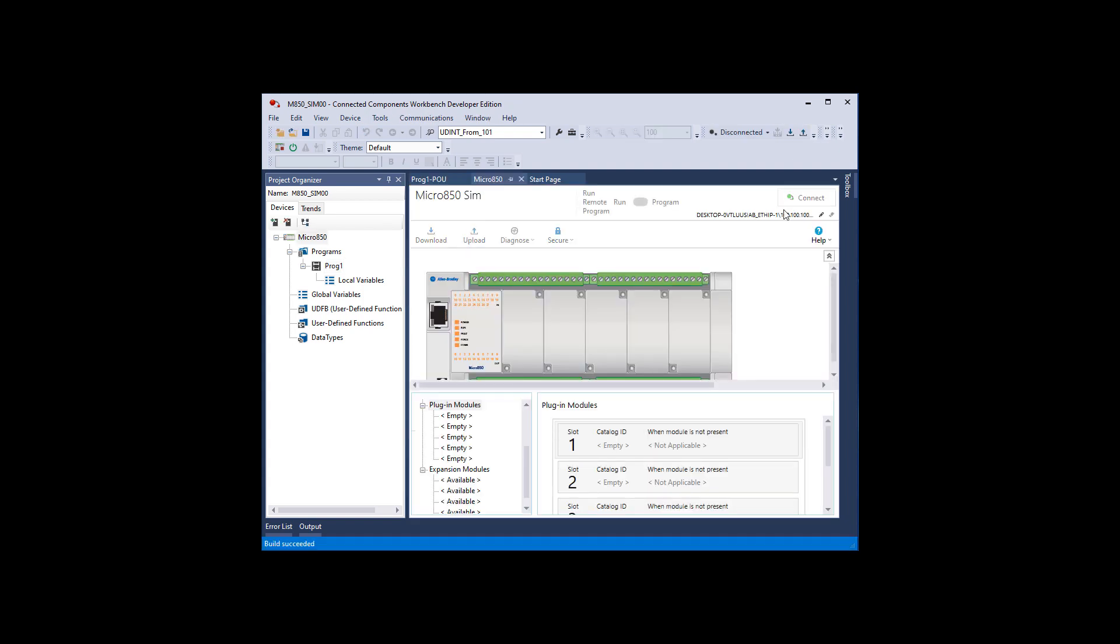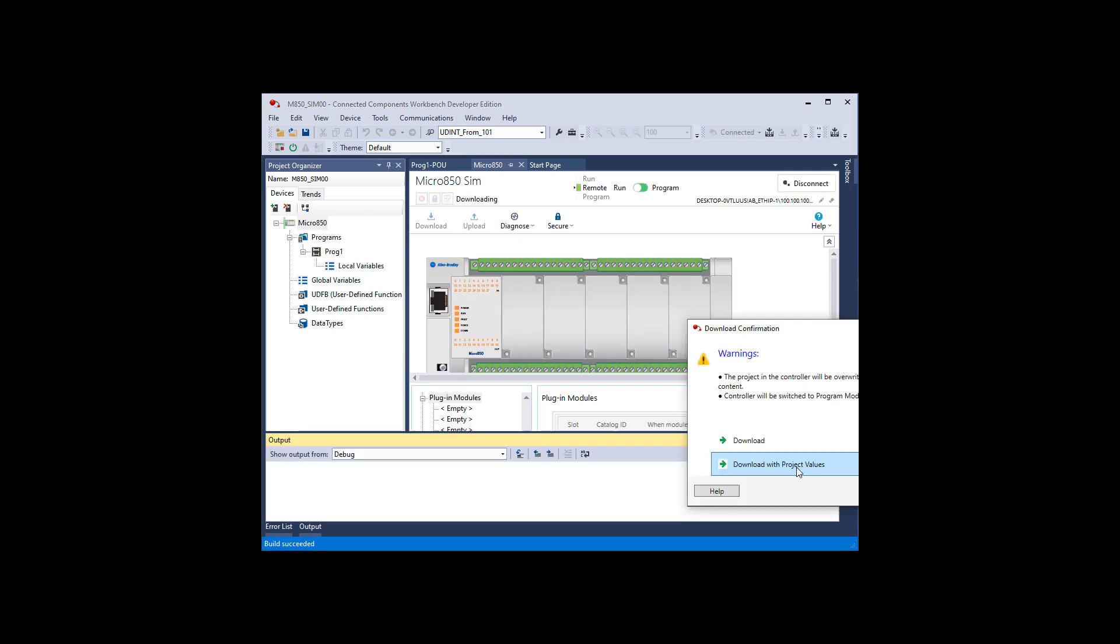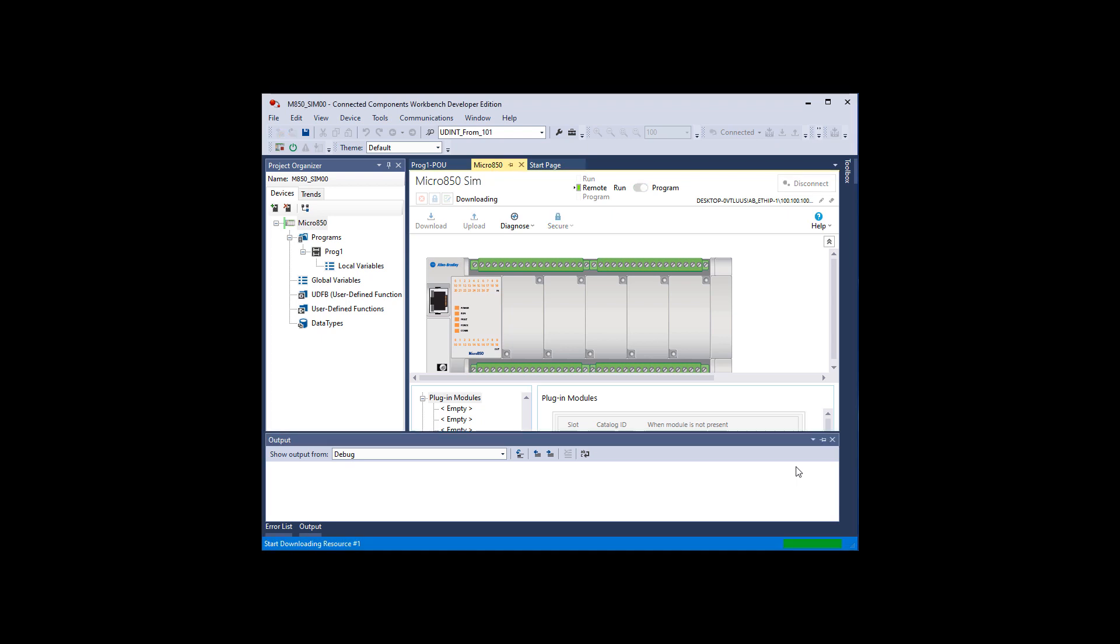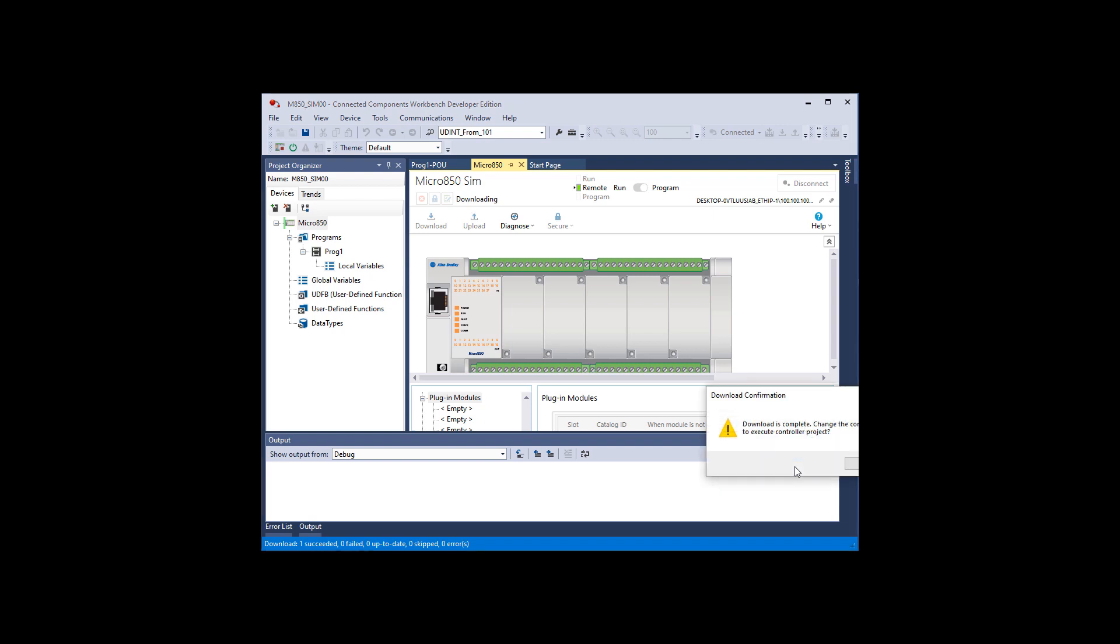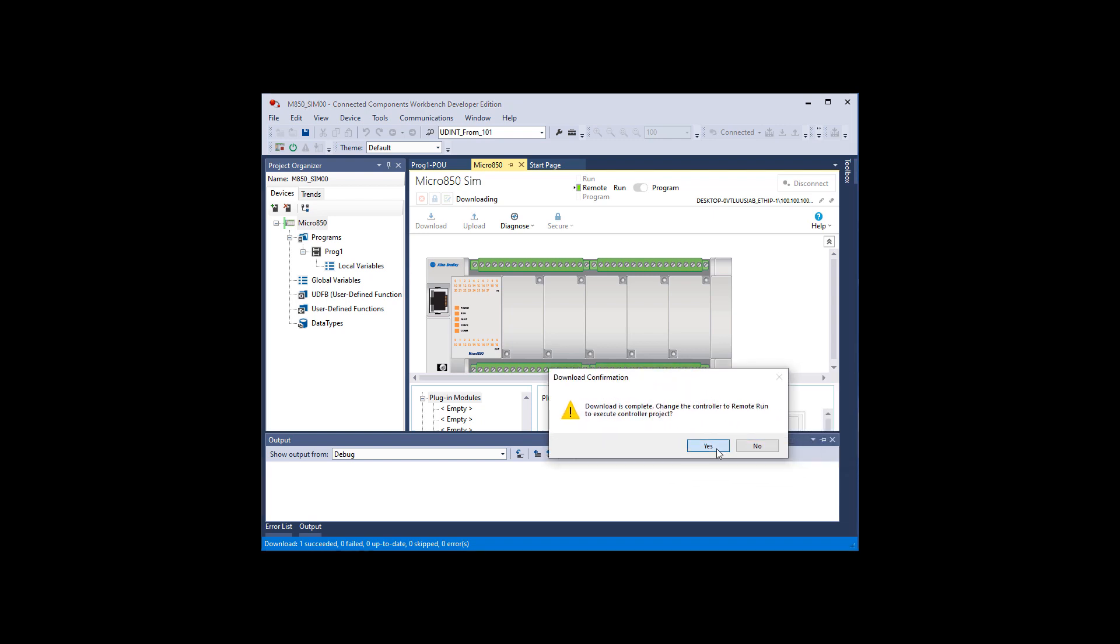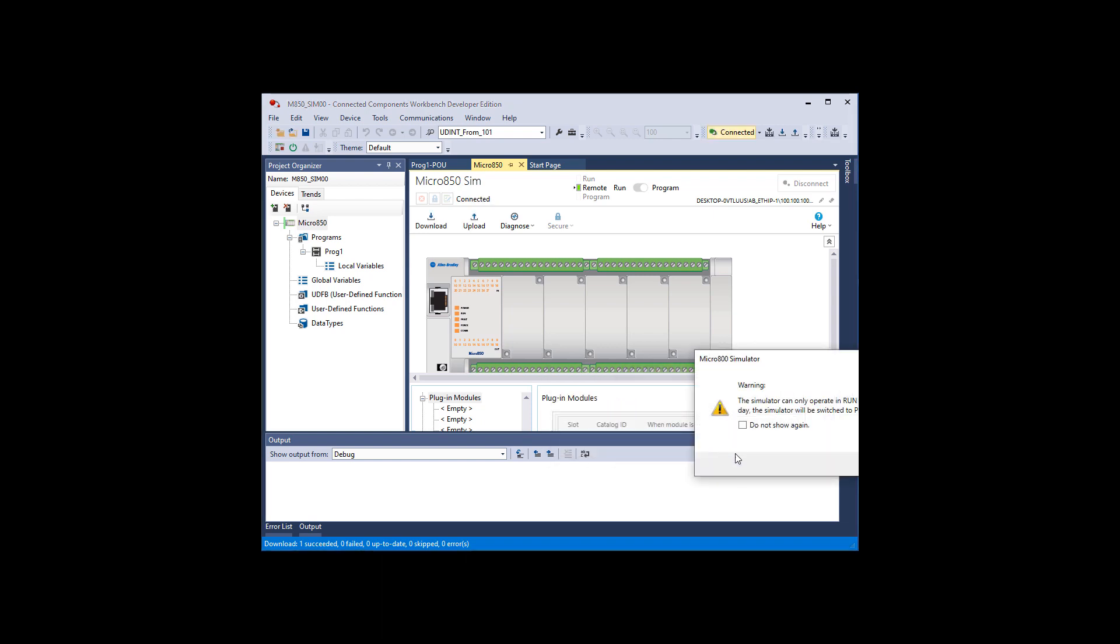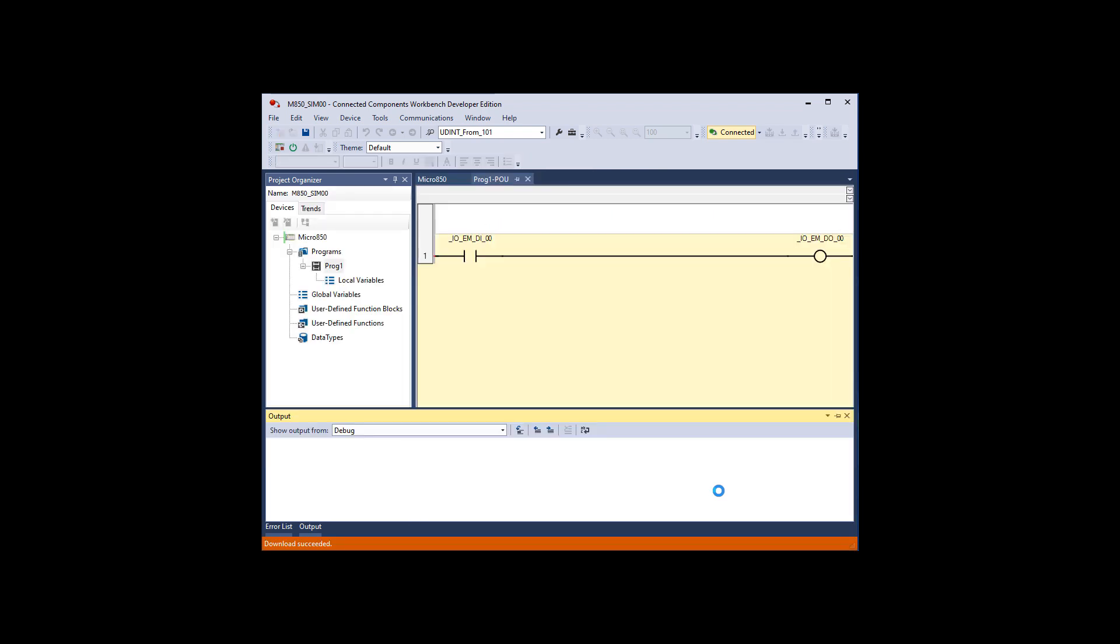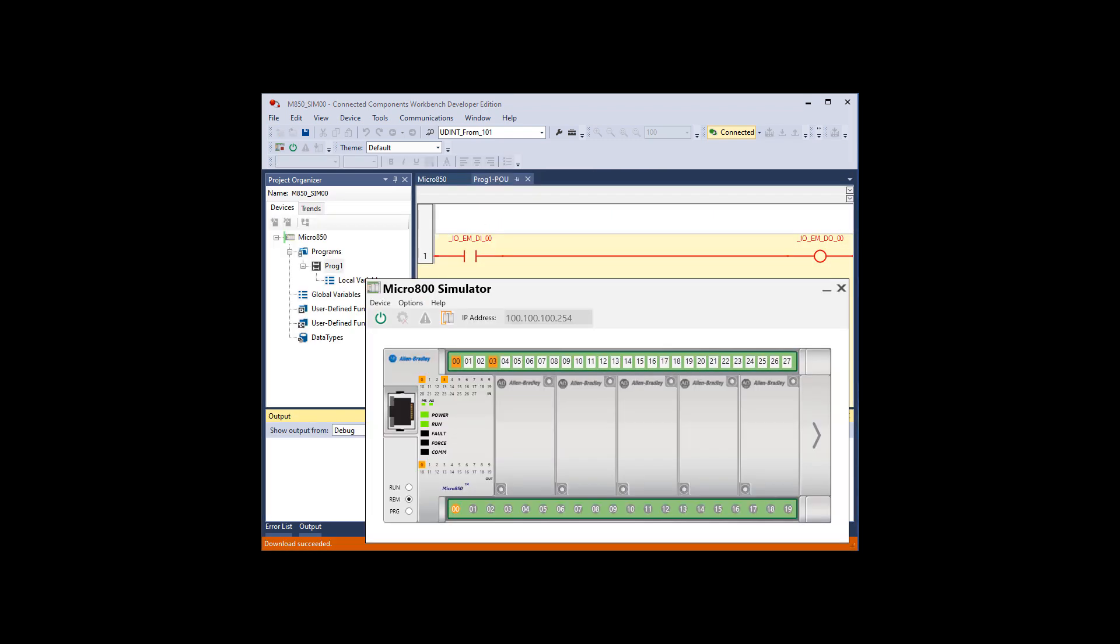Remember, you're already supposed to know how to do all this stuff. Let's download it. Download with project values. We really don't have any, but you want to get in the habit of downloading with project values until you get out on the shop floor and you're doing things on a live process. Then you got to be real careful what you're doing. You may not want to overwrite the values that are actually in the controller right at the moment. Okay, now we're downloaded and connected. Now, here's the challenge. I'm going to bring this back up and look, it's already on, so let me turn that off. See, the rung goes false. Turn input 0 on, the rung goes true, and this output down here goes on. Look at that. See how easy this is.